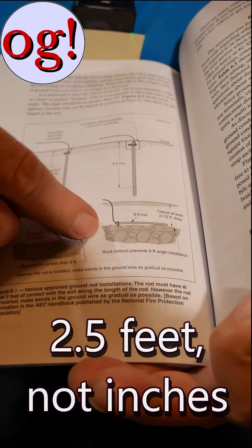This shows ground rods driven all the way down, a minimum of eight feet, with the whole eight feet under the ground. Now in the event that you have problems with rock bottom, try and get this at least two and a half feet deep. Lay the ground rod right on top of the rock and then bring the wire up like that. Or if you've got a couple feet, you can come in at an angle so that it's a little easier to tap.